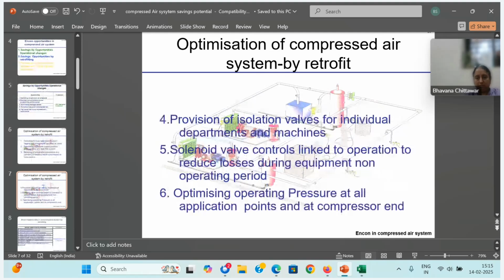Then provision of isolation valves for individual departments. Most of the factories, they are not running all the departments or production halls 24/7. Some operate only for one shift, some operate for two shifts, some operate for all three shifts. So if you have isolation, I prefer automatic isolation also. Whenever they switch off the machines, air supply should be cut off. Or for the department, they should cut off air supply, which is not happening nowadays, but it should happen. Because whatever leaks happening in this department can be totally eliminated.